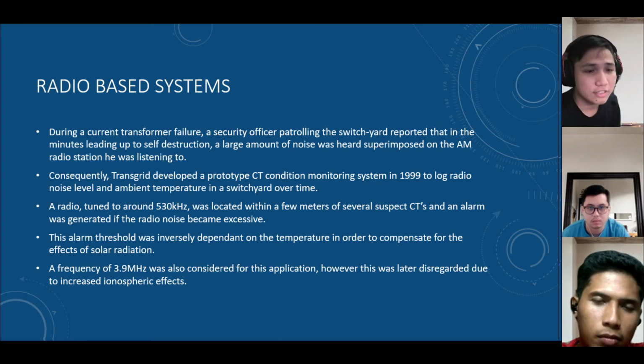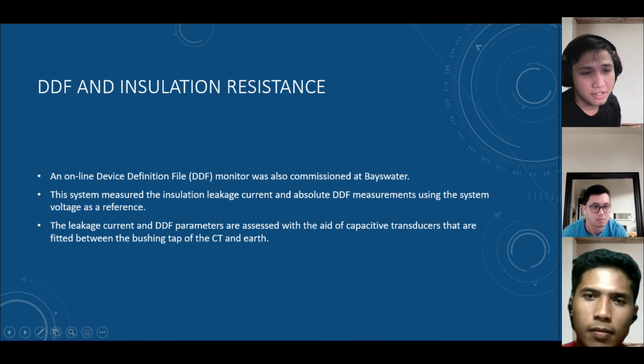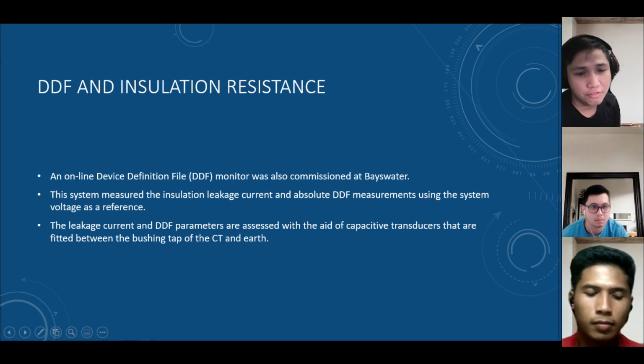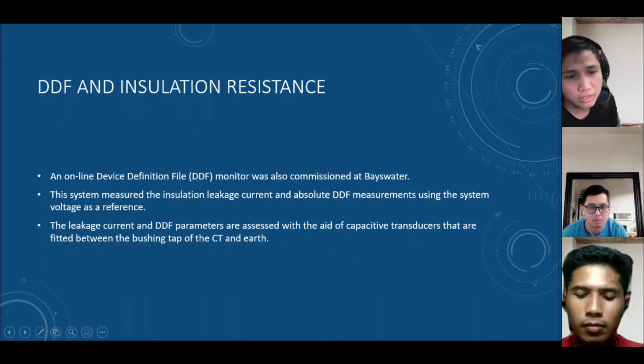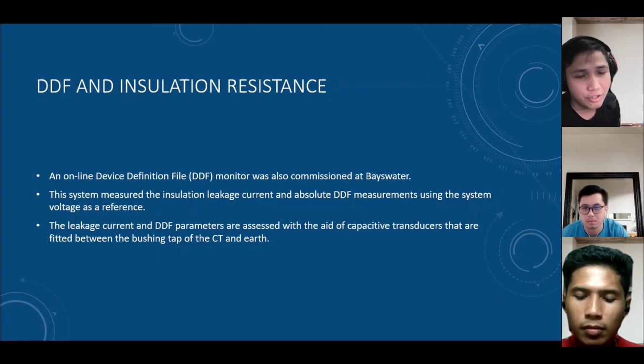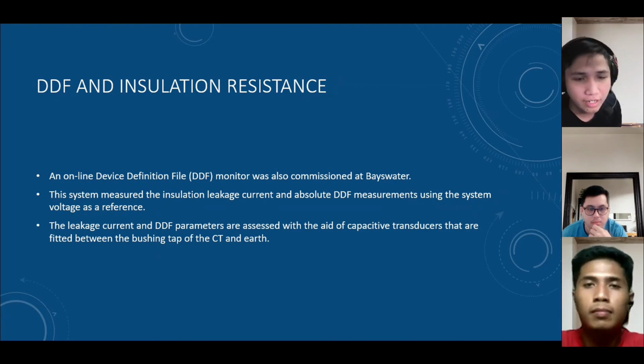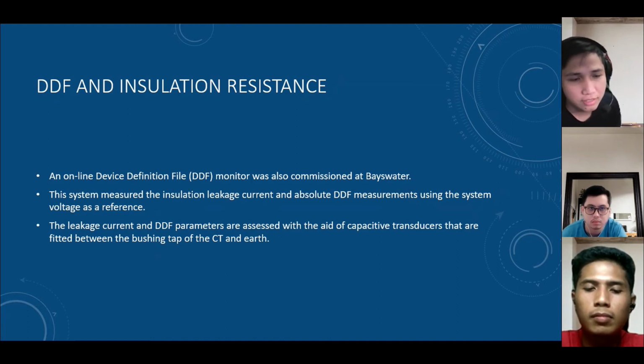And then the second one is DDF and insulation resistance. This DDF monitor was also commissioned at Bayswater. This system measures the insulation leakage current and absolute DDF using the system voltage as reference. The leakage current and DDF parameters are assessed with the aid of capacitive transducers that are fitted between the bushing tap and earth.